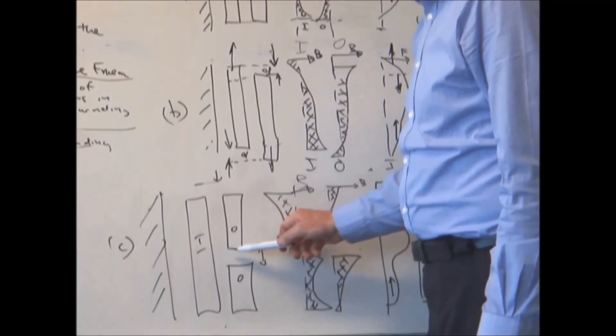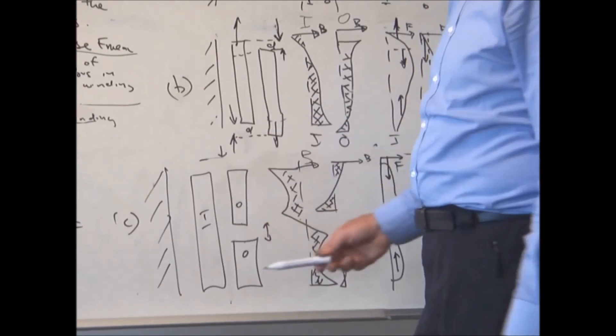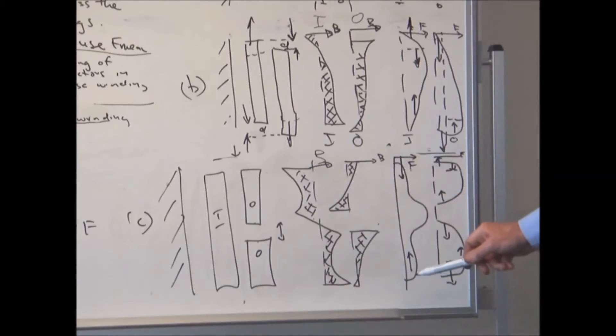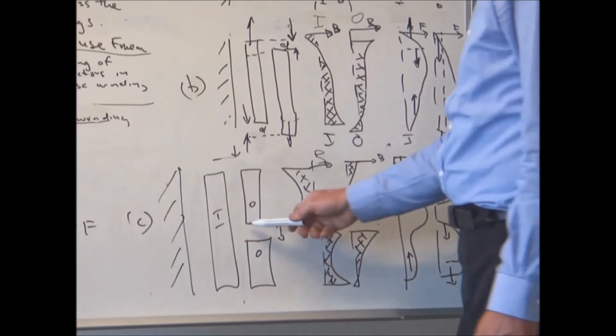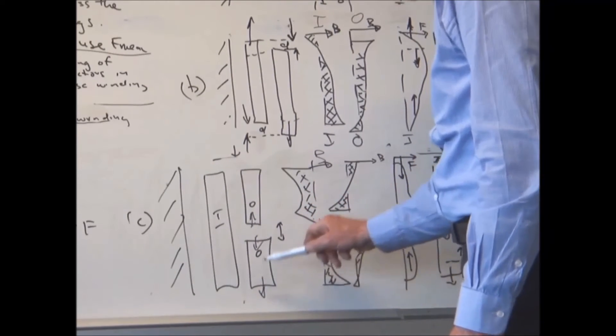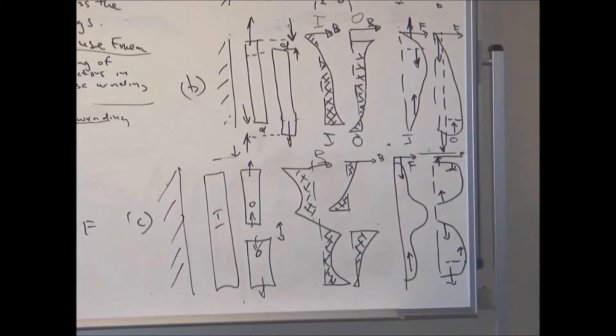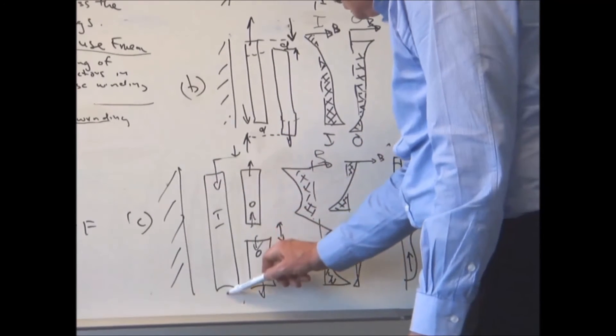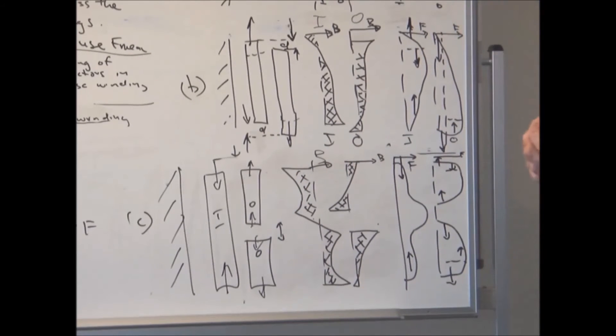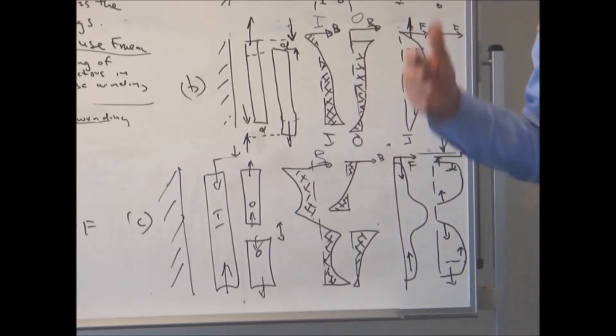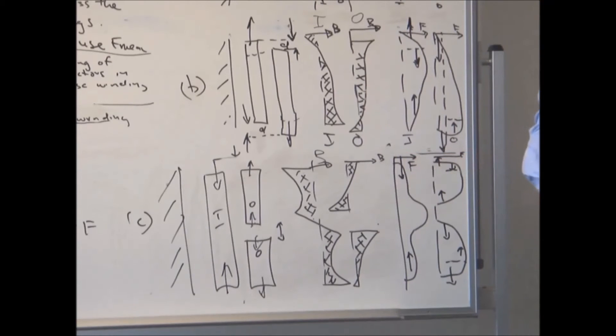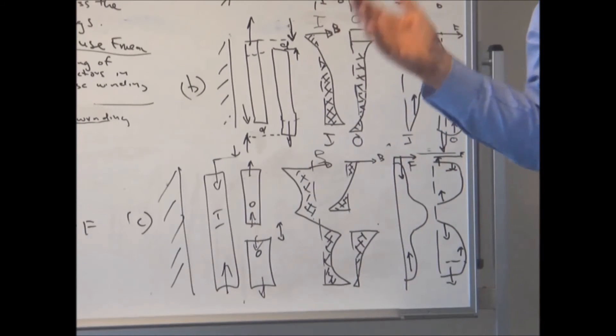Another case is when you have a gap on the outer winding — which you might have in high voltage windings — with the outer winding split into two. Now the field is radically displaced and different. There are forces on the inner winding and upward forces on the outer winding sections, plus downward forces and upward forces at other locations. The outer winding, which may be the high voltage winding, now has axial force components at the top and bottom. Gaps and displacement in the windings can radically change the field and therefore the force distribution.